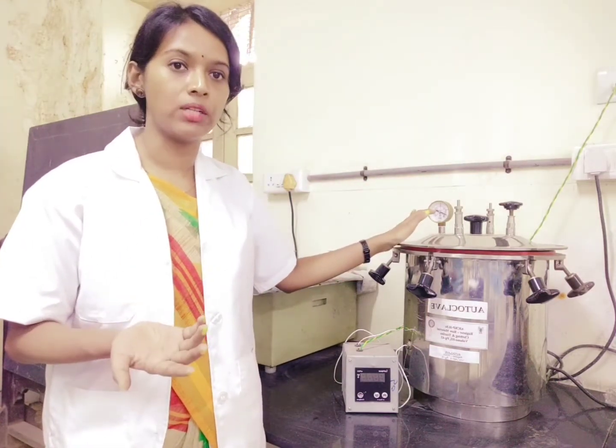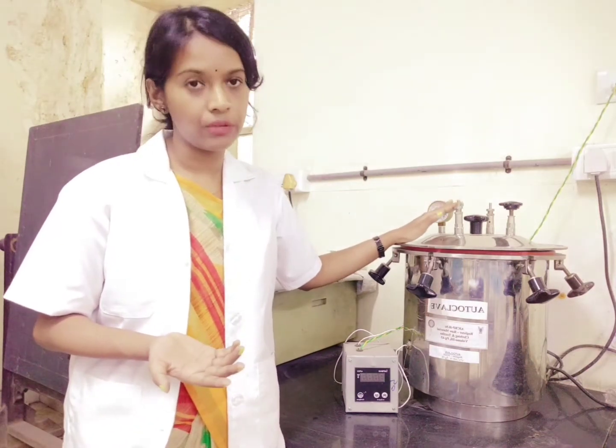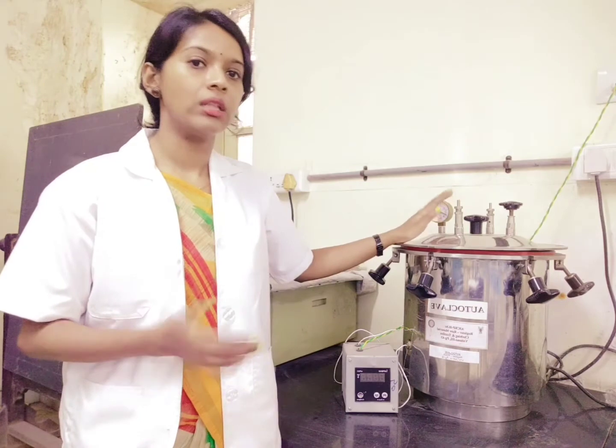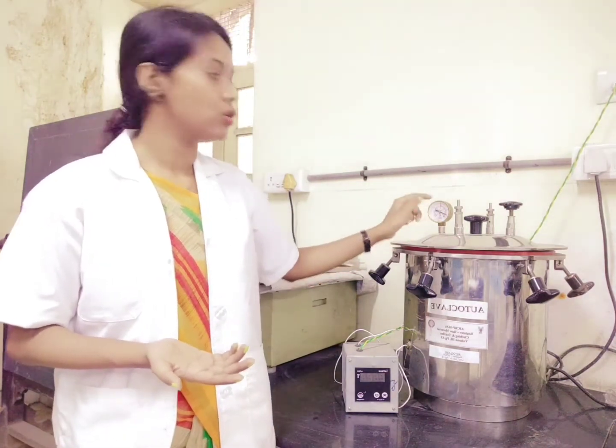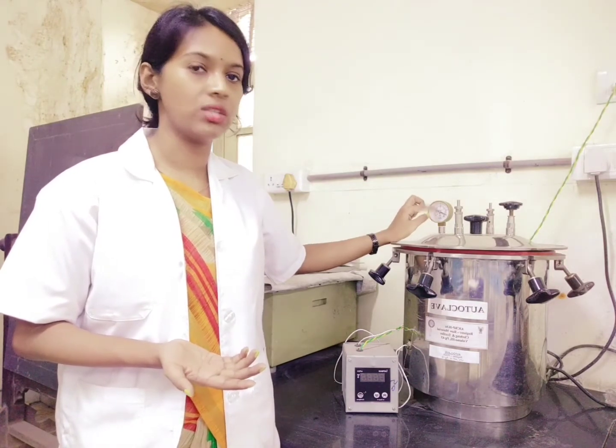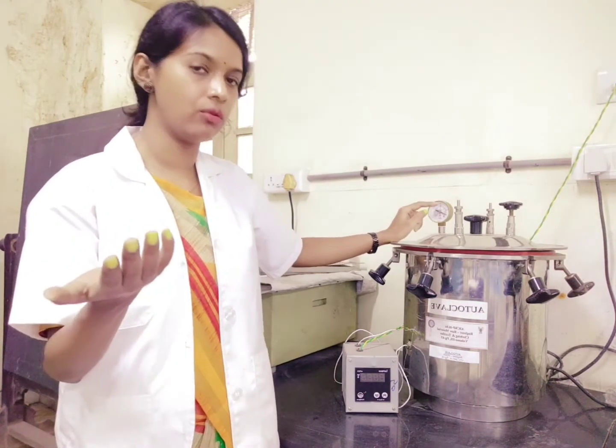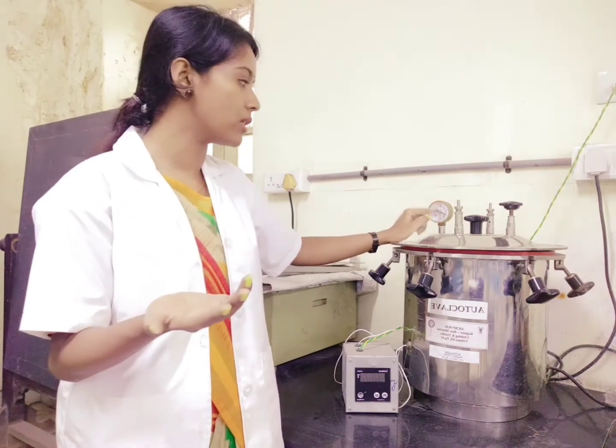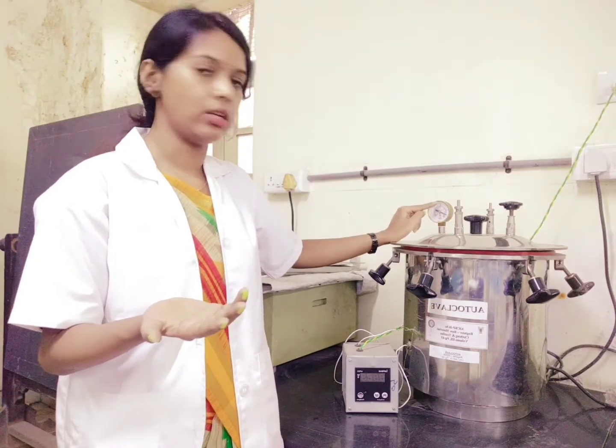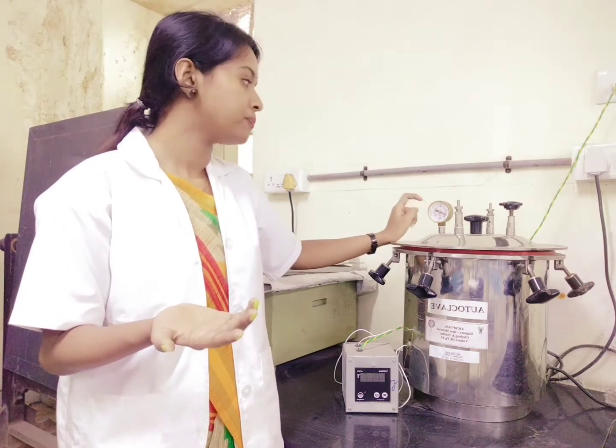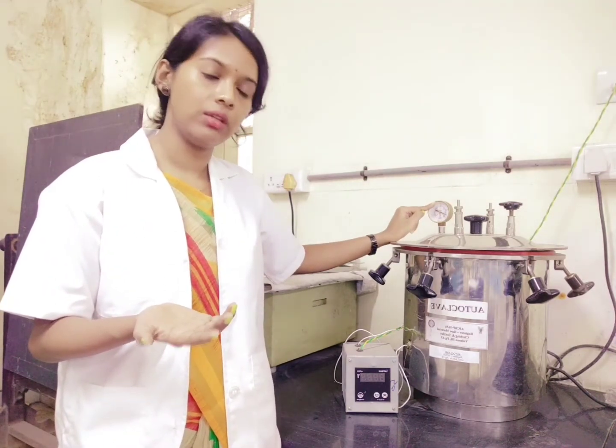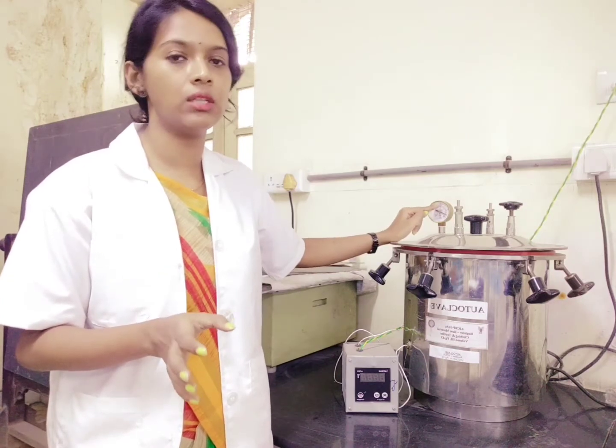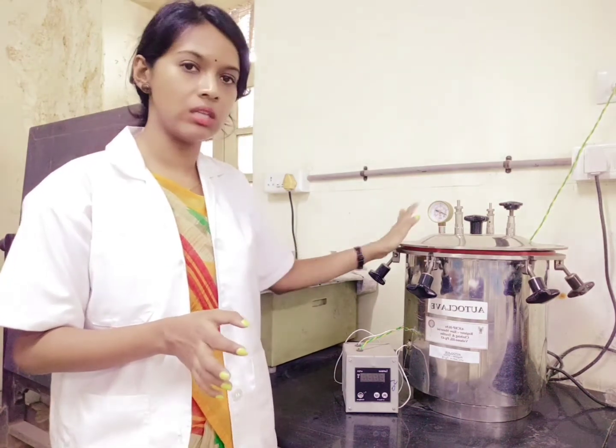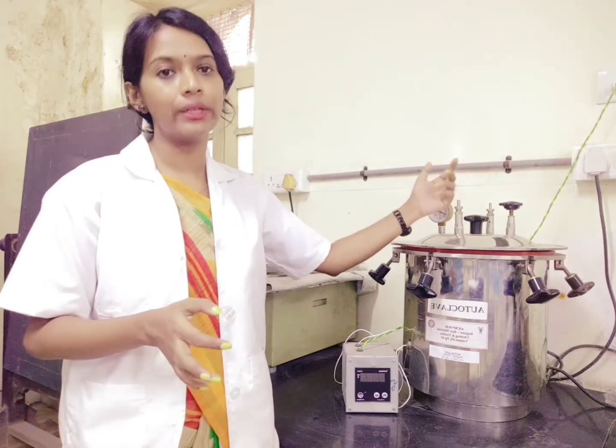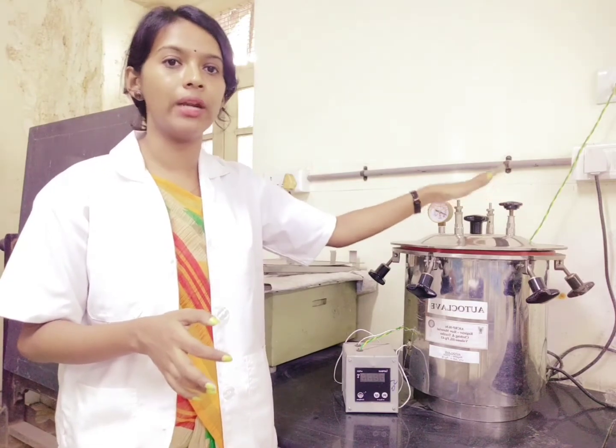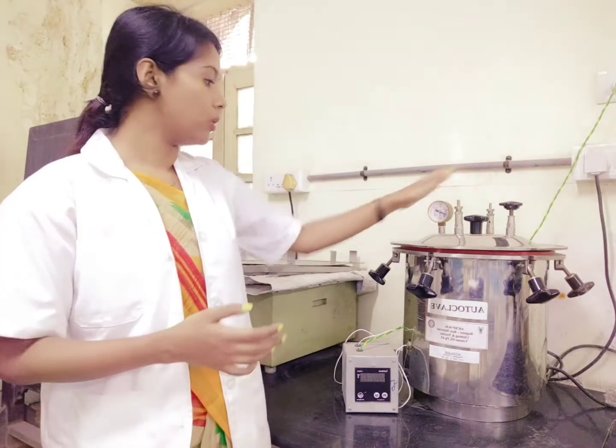In case the instrument is automatic, once it reaches 15 psi at 121 degrees, then automatically after 20 minutes the pressure will be released. Here you can see the pressure gauge, which shows how much pressure has built up inside. If you take a very close look, you can see this needle. On the center top, 15 is mentioned, that is 15 psi. Once the needle reaches 15, it will stay there for around 15 to 20 minutes, then automatically the needle will come down, meaning the pressure is released. Since this one is not automated, we have to manually open the valve and let the pressure release. So that is about this instrument.